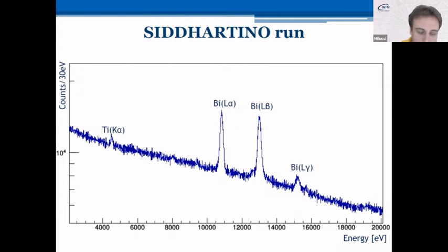This is the typical global spectrum collected, and here you can see clearly four peaks. There is the titanium K alpha, which is activated by the showering effect, the particles hitting the top of the target cell, and the three peaks which are the bismuth L alpha, L beta, and L gamma, which are all the possible L transitions of the bismuth. And the bismuth is present behind the silicon wafer of the SDD detectors, and is also activated by the beams. For the rest, in the energy region that we are more interested in, which is from 5 to 10 keV, it is quite clean. There are no spurious peaks in this region.